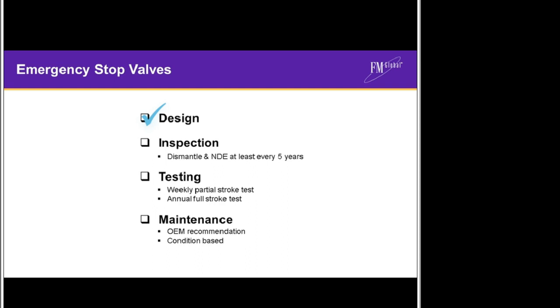Partial stroke testing proves freedom of movement and should be completed weekly. However, that frequency can be decreased to monthly if all necessary steps have been taken to minimize risks on the turbine. These include maintaining impeccable water chemistry, comprehensive test records, taking immediate action on any deficiencies that are found, annual overspeed testing and after significant maintenance, and full stroke testing on an annual basis. Finally, maintenance should be completed according to OEM recommendations or as conditions determine.